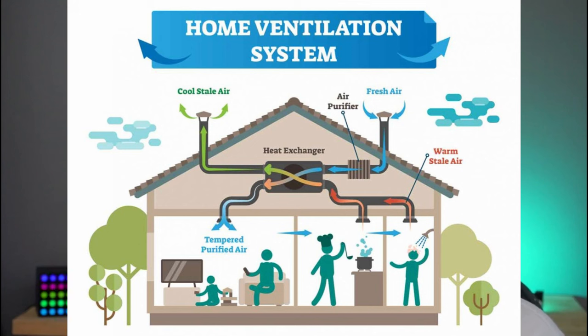Modern houses are being built much more airtight and with far more insulation. Because of this, we need to consider ventilation. We need to get rid of old stale impurities such as CO2, volatile organic compounds, as well as moisture, most importantly. So in order to do this, we ideally need a two-fan system. One fan to draw the damp air from bathrooms and kitchens, and another one to supply fresh air to areas like bedrooms and living areas.